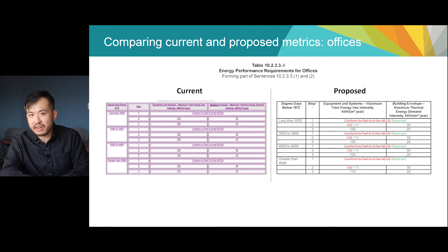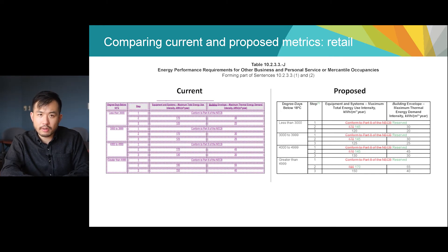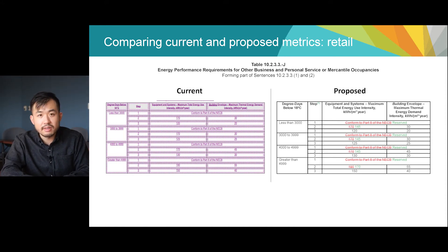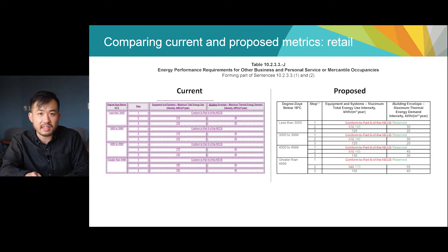These new step two targets present a range of energy savings compared to NECB depending on the size and shape of the building. For a more detailed analysis on how the new targets compare to the old ones, read the update to the metrics research report, available alongside other supplementary materials on gov.bc.ca/buildingcodes. On the left in purple are the current step code metrics for retail occupancies, and on the right are the proposed changes. In climate zones 4 through 6, the TEUI targets are set to 145 instead of 170. In colder climates, the TEUI targets are set to 170 instead of 190. TEDI targets again remain the same. For more information, review the update to the metrics research report on gov.bc.ca/buildingcodes.